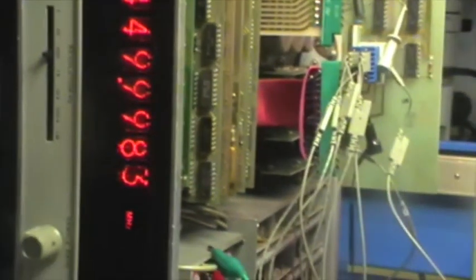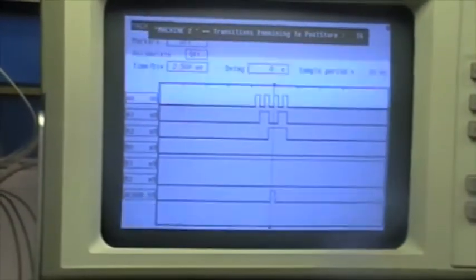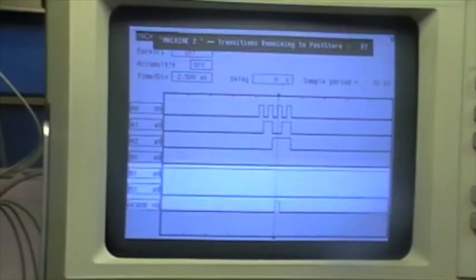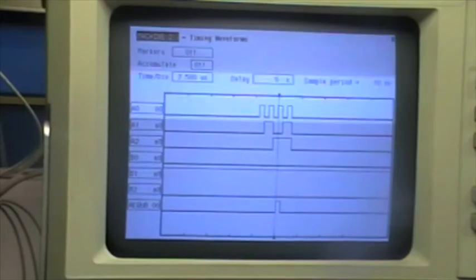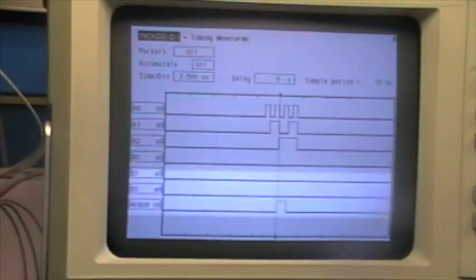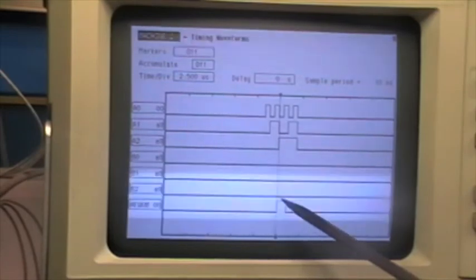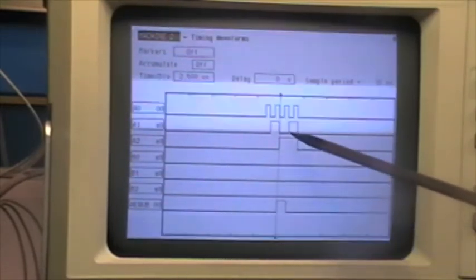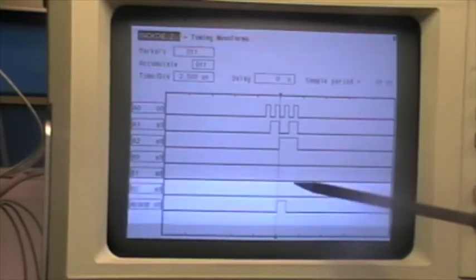So, as you can see here, I'm having an output, right? And the counter is counting right. I have my signal generator at 450. Well, of course, you need to calibrate the instrument, but we are almost there. So if I switch to another range, let's say 1K resolution, as you can see here, the output is not as it should be.